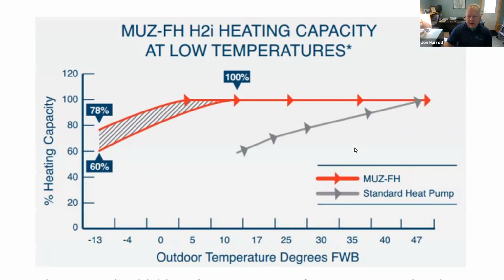Cold climate heat pumps, which first started to become common in our area about 10 years ago, and now have a really strong track record in our region, maintain their performance at 100% all the way down to 5 degrees or so. Below that, they start to fall off, but they still maintain a significant portion of their output all the way down to temperatures that we rarely encounter in our region. So it's important to understand the performance of these systems at low temperatures when you're designing a system, but the technology is proven and the heating curves are well known, so we can take that into account when we're designing these systems.